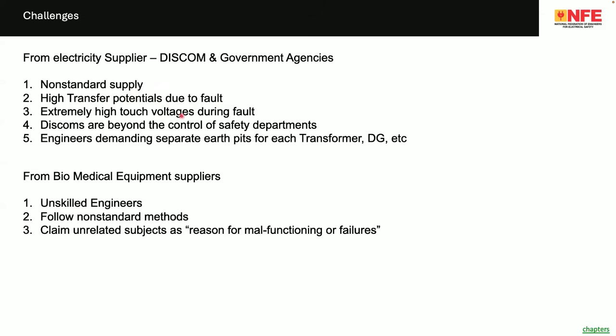and the arcing results in fire. Extremely high touch voltage during fault. DISCOMs are beyond the control of the safety departments, in the sense, even if somebody tells them to make it proper, of course, nobody is going to listen to you. The DISCOM is not going to listen. Engineers demand separate earth pit for transformer, DG, etc. Sometimes even the authorities, those who are supposed to ensure safety, are violating the requirement. Like they ask for separate earth pit for DG, separate earth pit for transformer, and so on.